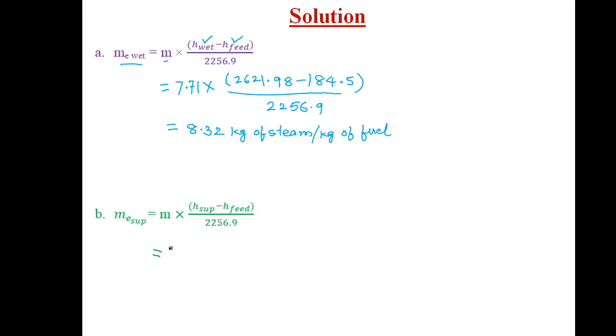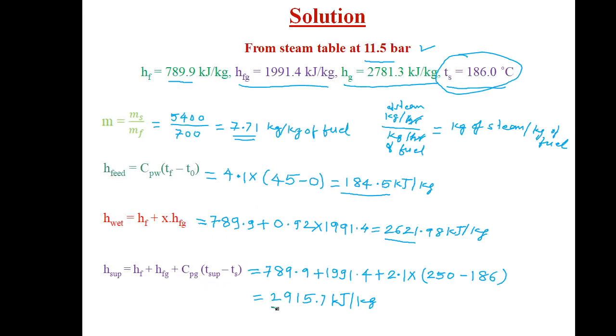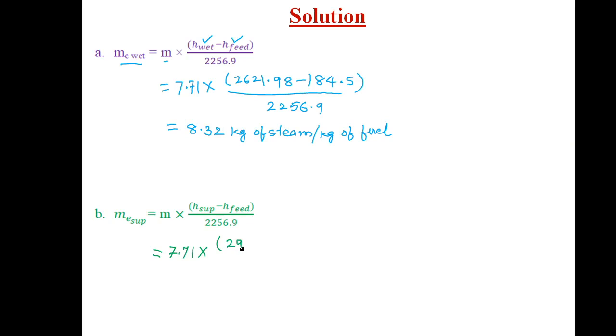In a similar way, equivalent evaporation for superheated steam: mass m = 7.71 kg of steam per kg of fuel burned, enthalpy of superheated steam = 2915.7, minus enthalpy of feed water = 184.5, divided by 2256.9. On further simplification, equivalent evaporation of superheated steam works out to be 9.33 kg of steam per kg of fuel.